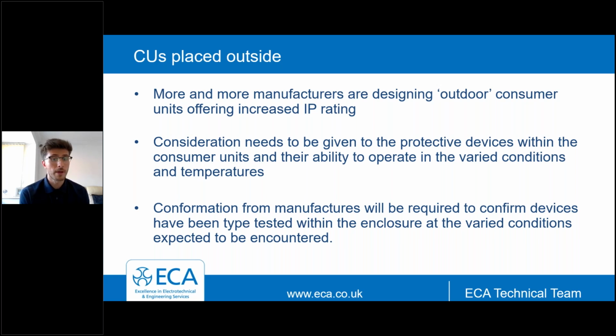So you're going to need to obtain confirmation from manufacturers that the devices have been type tested within these enclosures, at the varied conditions that would be expected to be encountered throughout the different seasons and temperatures, and clarity that the IP rating is actually going to be maintained and intact. Manufacturers should be able to provide you certification on this, if that is the case, or a declaration of conformity to confirm that their equipment is actually suitable. So we're not completely ruling this one out, but you need to carry out some further due diligence if looking to apply this measure and confirm that what you select is actually suitable. It's more than just IP rating that needs to be considered.